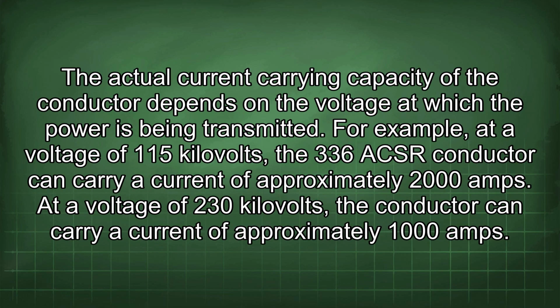The actual current carrying capacity of the conductor depends on the voltage at which the power is being transmitted. For example, at a voltage of 115 kV, the 336 ACSR conductor can carry a current of approximately 2000 amps. At a voltage of 230 kV, the conductor can carry a current of approximately 1000 amps.